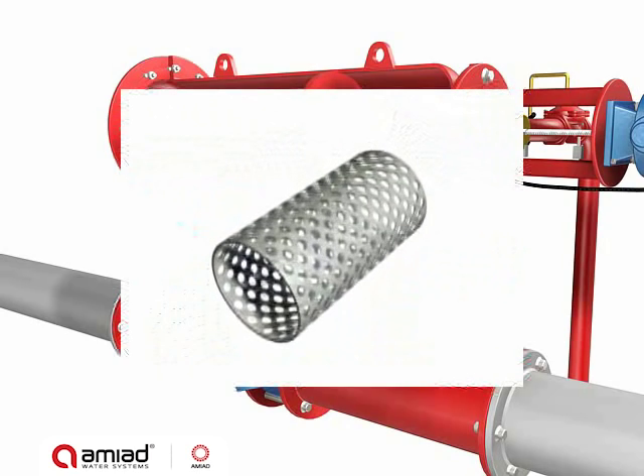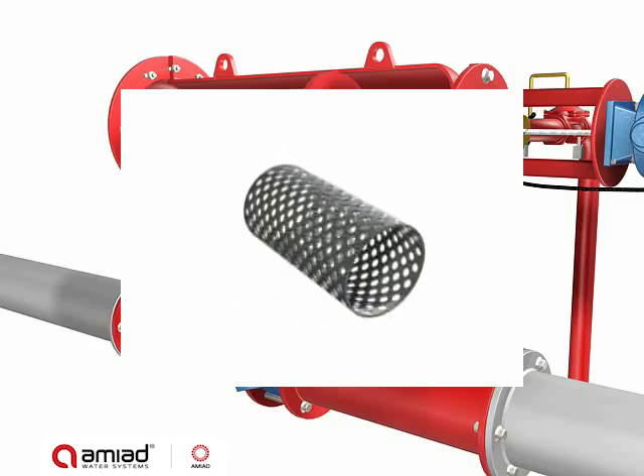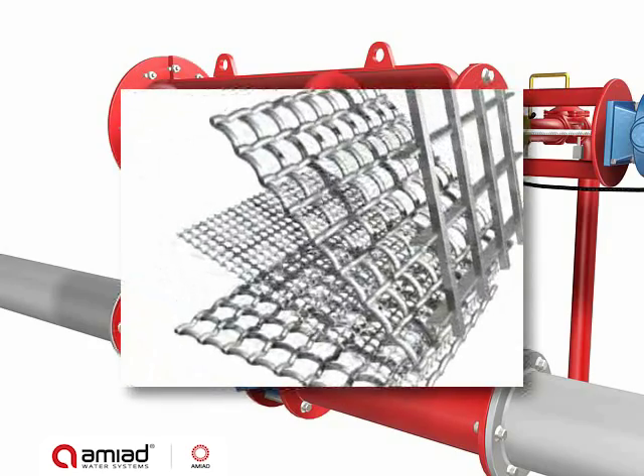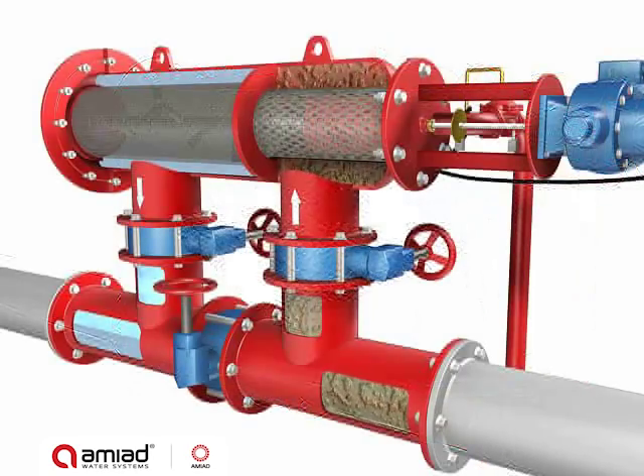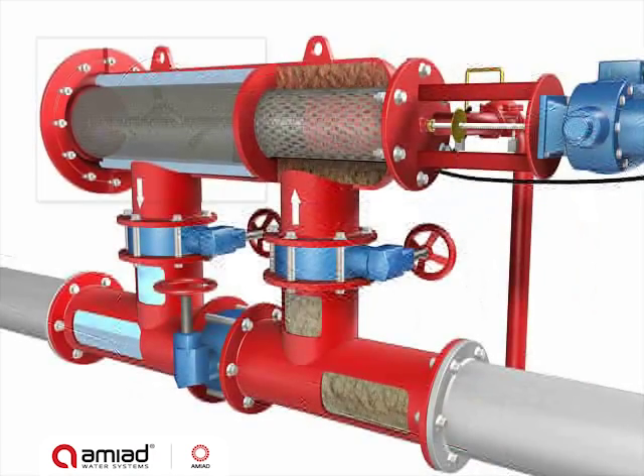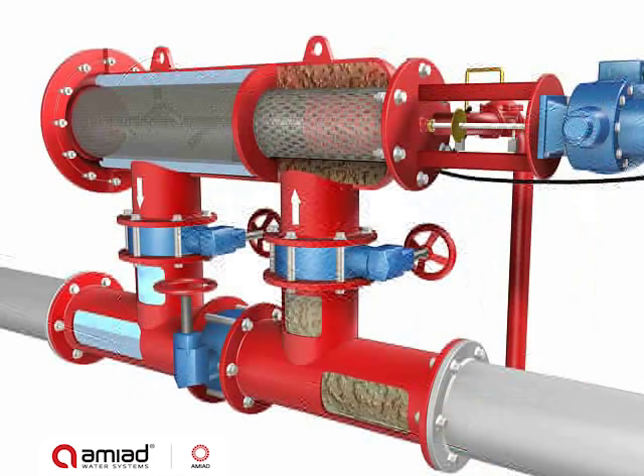The filter housing contains two screens: a perforated coarse screen for capturing large dirt particles, and a multi-layer fine screen for capturing debris larger than the micron rating of the screen. The raw water enters the inlet pipe through the coarse screen from the outside in, then passes through the fine screen from the inside out.